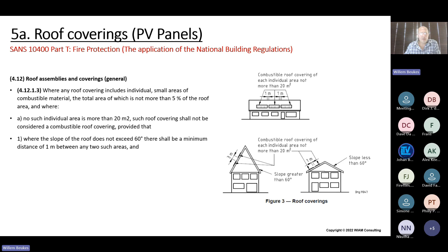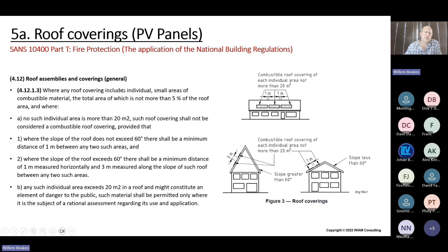And if you don't have any of these in place, you have to have a rational design from a fire engineer. Now, we use this concept as a guidance also in large scale, even where the roof area component is more than 5% of the roof. A practical installation will look like this, where you have at least 1 meter gap between your sections of strings. You will try to keep your sections of strings at around 20 square meters per installation, so that the propagation on these panels will be controlled in grouping format.